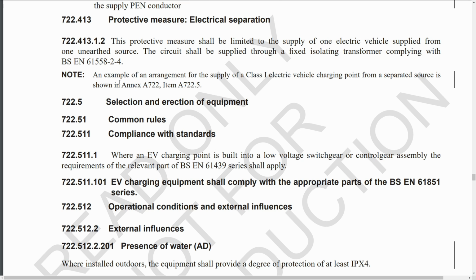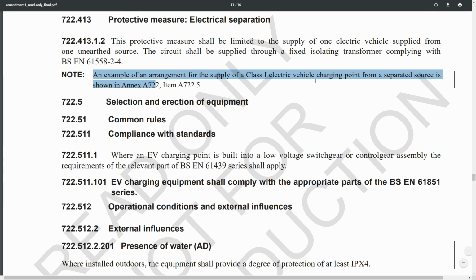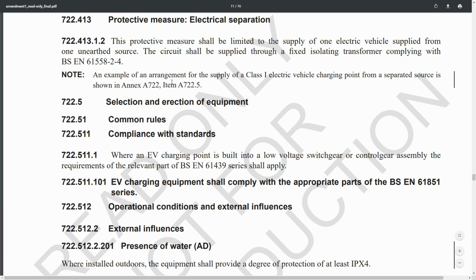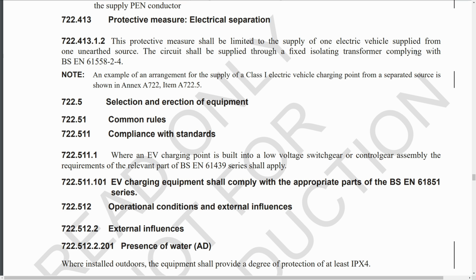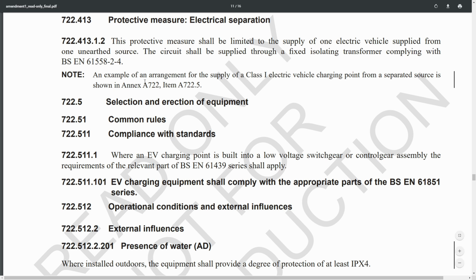There's a couple of notes here which have been revised somewhat. This note here just says an example of the arrangement for a Class 1 electric vehicle from a separated source. It's shown there. Electrical separation isn't, again, a very likely one because it needs to be supplied, it says there, through a fixed isolating transformer. Entirely possible, but that is going to massively increase the cost of the installation, because an isolating transformer suitable to supply an electric charge point even at, say, 7 kilowatts or so, that is a huge piece of equipment. It's going to be extremely expensive, and of course if you're going to have more than one charging point, you're going to have an even bigger transformer, and you're going to have one per point and so on. So just a note there of a possible arrangement in the annex.